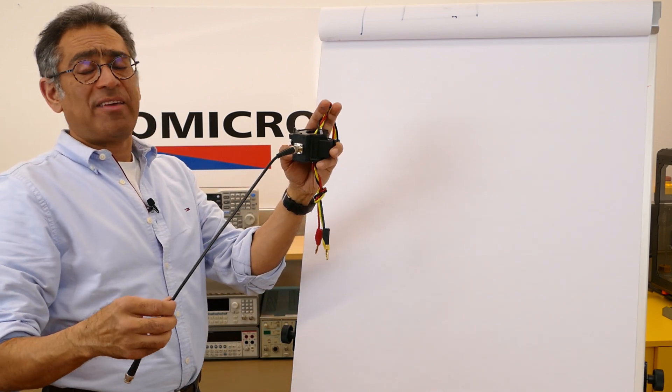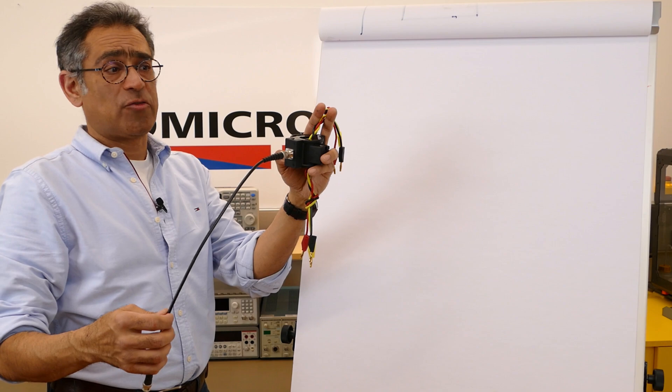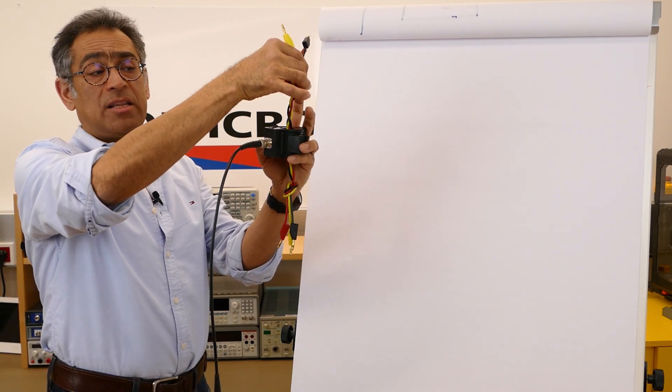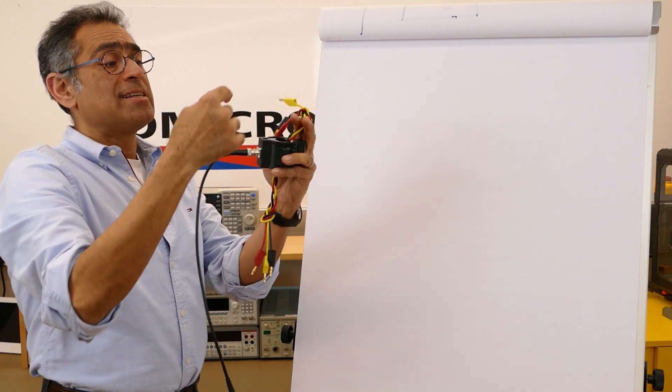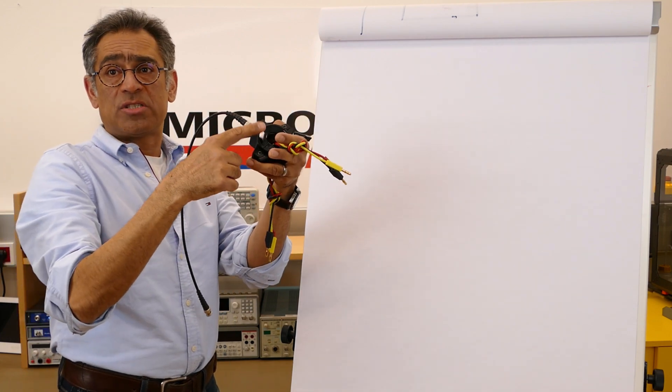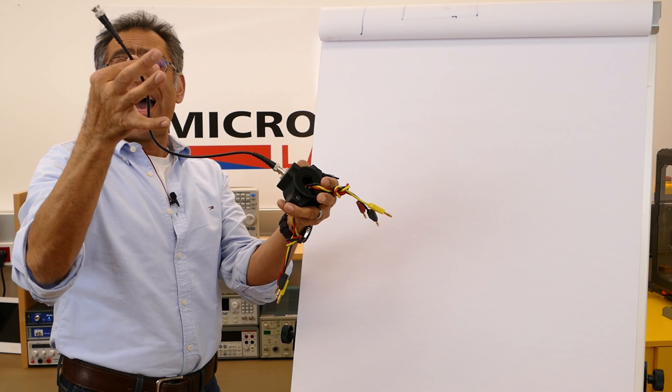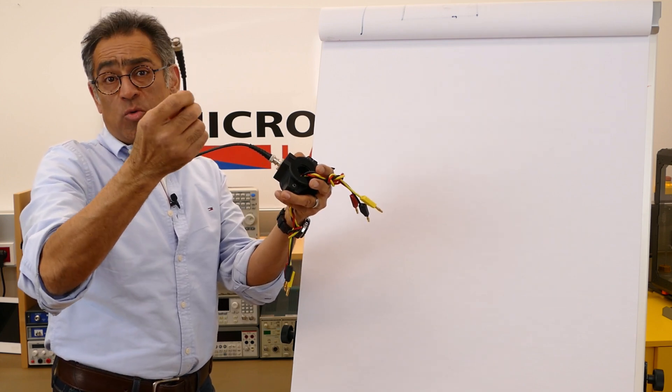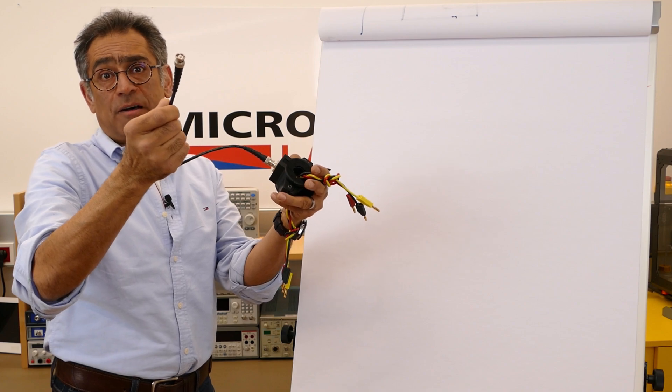So in effect what you have here is a current transformer whereby you've got one single turn on the primary, that is the cable of your device under test, several turns on the secondary which is inside of the current clamp, and then the output of that is going to go to a spectrum analyzer which has got an impedance of 50 ohms.